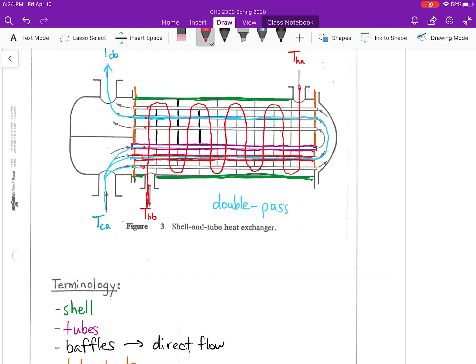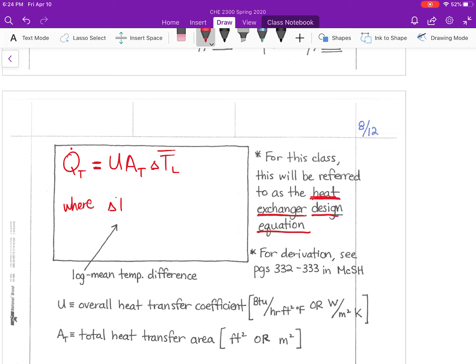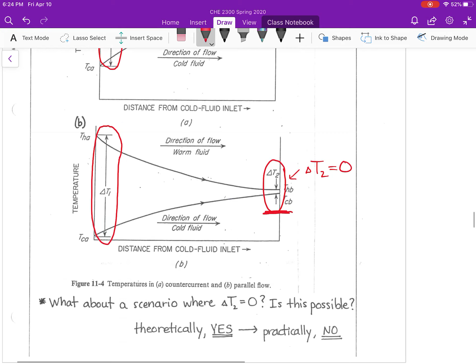Heat flow equals the overall heat transfer coefficient times the total area, multiplied by the log mean temperature difference, where the log mean temperature difference, in terms of delta T1 and delta T2, is equal to delta T2 minus delta T1, divided by the natural log of the ratio of those two approach temperatures. This is our heat exchanger design equation.